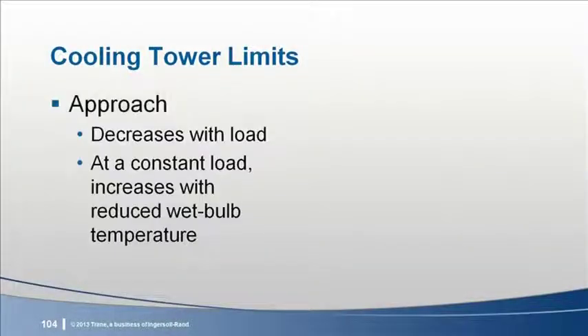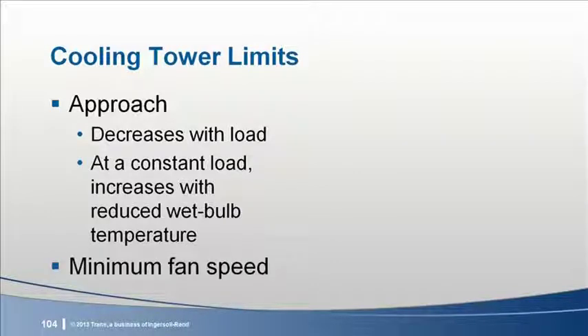The first limitation for a cooling tower is its approach to the outdoor wet bulb temperature. As the load is reduced, the approach temperature decreases, which allows colder leaving tower water temperature. Physics also tells us that at the same heat rejection load, as the wet bulb drops, the approach temperature actually increases. So that means that the water is colder, but not as cold as we might have guessed. The second limit is that the tower fan VSD will have a minimum speed.